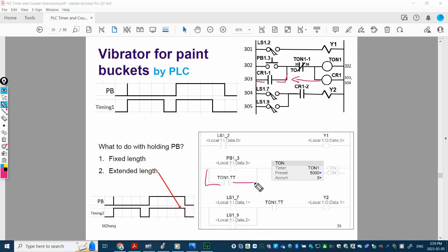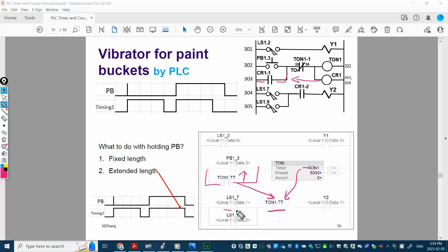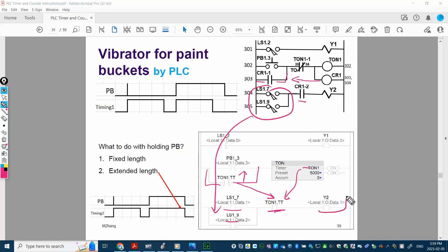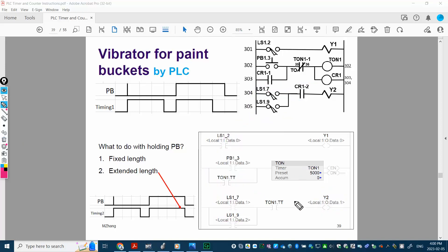In the electrical design we used a control relay contact to seal in the circuit, but in PLC we don't need that. We can use the TT bit directly to seal in — to latch — the push button. With the timer running, we use the TT bit not only for seal-in but also for timing. Between the two limit switches, just like in the relay design, we can translate that directly in parallel. When we have the TT bit active, we directly energize Y2. That's the PLC design for the bucket shaker.